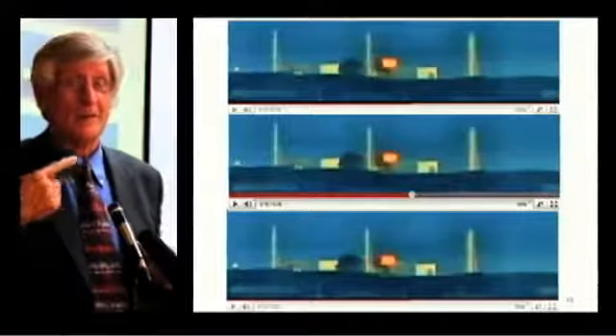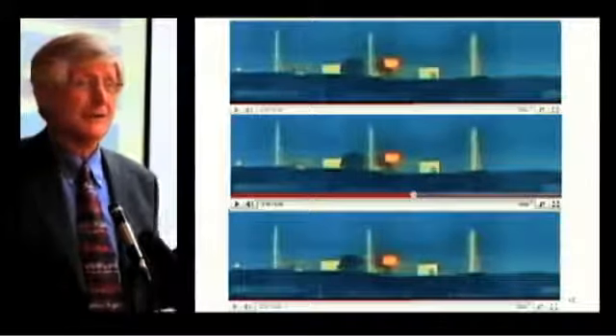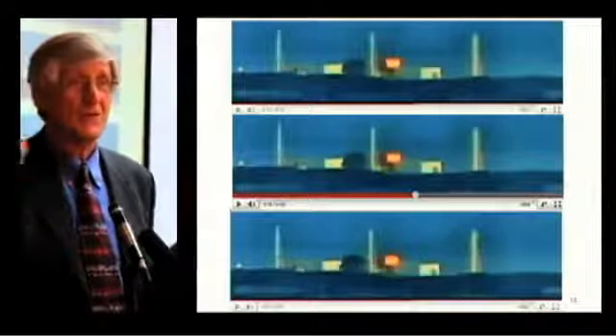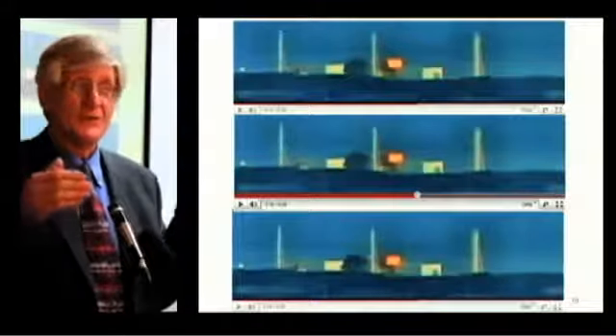The Challenger explosion technically was a deflagration, and we all know that that was catastrophic. But this is worse because the wave front, just basically the pressure of the wave and the speed of the wave, can do enormous damage. This is a problem on all reactors because no one knows why this happened. Hydrogen and oxygen at room pressures shouldn't detonate. I talked to a bunch of chemists, and we can't figure out how hydrogen and oxygen could detonate. It can deflagrate, like the Hindenburg, but it shouldn't be able to detonate.